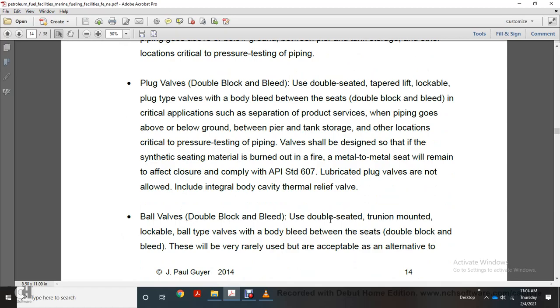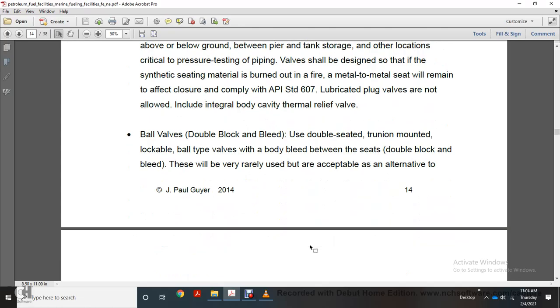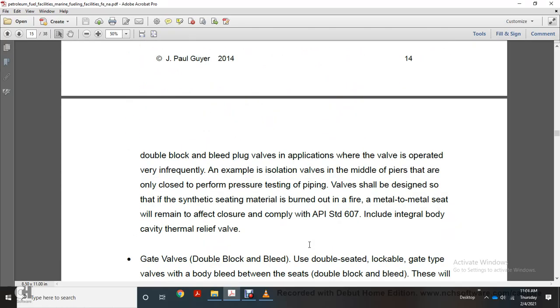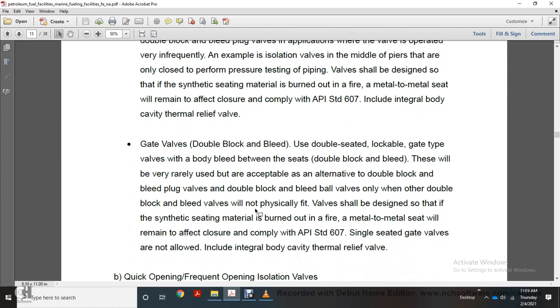Ball valves, double block and bleed. Use a double-seated, trunnion mounted, lockable ball type valve with a body bleed between seats for double block and bleed. These will very rarely be used, except as an alternative to the double block and bleed plug valve in an application where the valve is operated infrequently, for example an isolation valve in the middle of the piers that is only closed to perform pressure testing of the piping. Valves should be designed so if the synthetic seating material is burned out in a fire. Metal to metal seats remain effective for closure. Comply with API standard 607. Include an integral body cavity thermal relief valve.